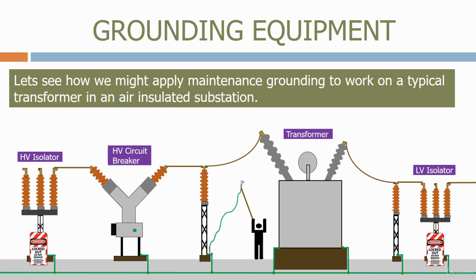It's very important that we always connect the ground lead to the substation ground grid before we connect it to the equipment being grounded. Once the lead is connected to the ground grid, we use an insulated pole to connect it to the high voltage conductor. We then use the pole to tighten the grounding clamp to get a good electrical connection on the conductor.